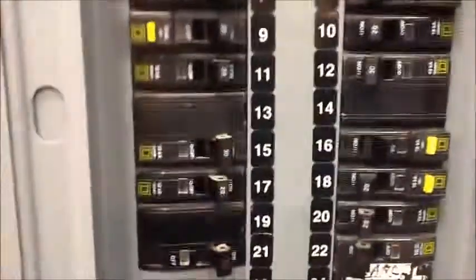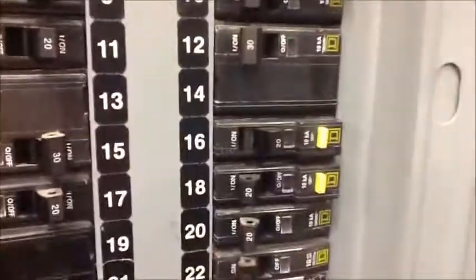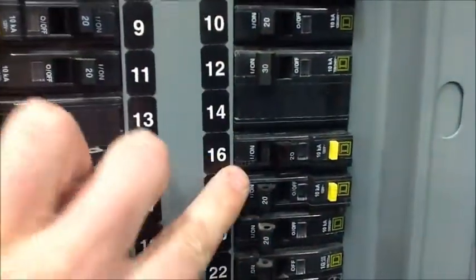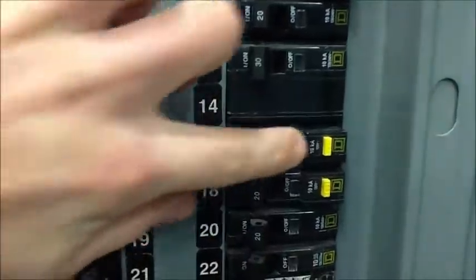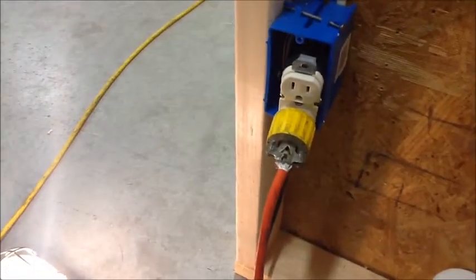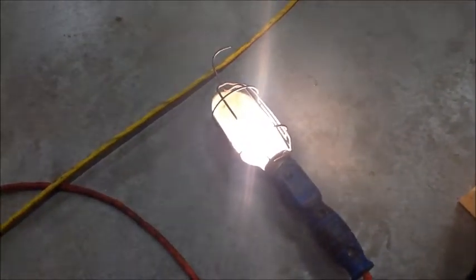You're going to come back over here, and you're going to take your circuit breaker that you shut off earlier, right here. See, it's in the off position. And you're just going to flip it back over, and you're going to come over, plug your lamp or whatever you have, radio, plug checker, anything you have, into the receptacle you just installed. Verify that it's working properly.